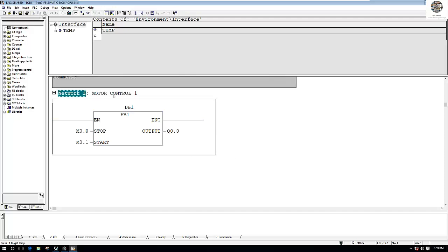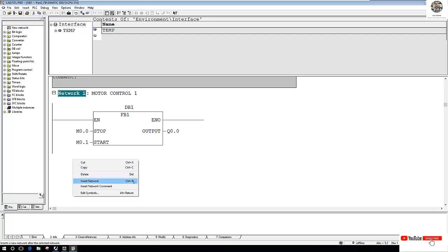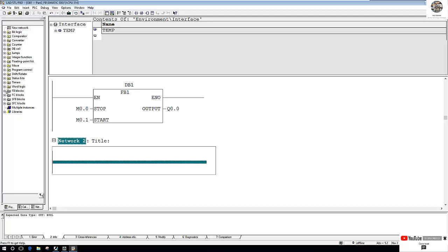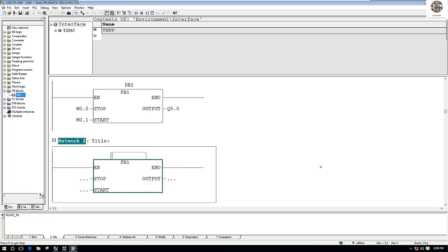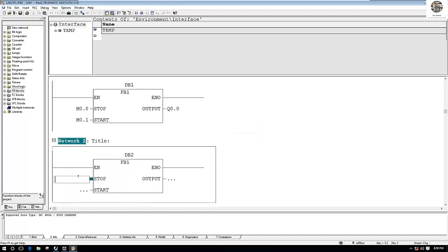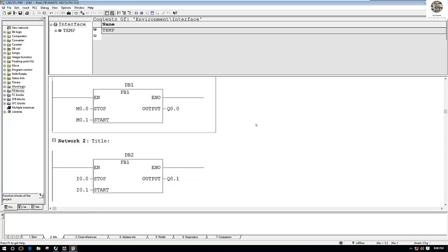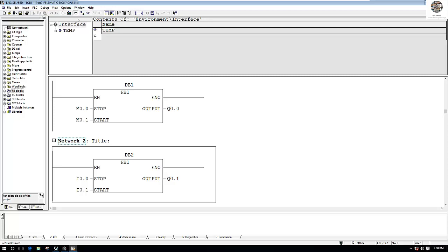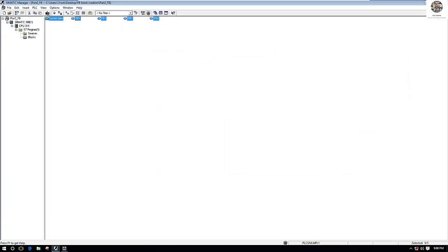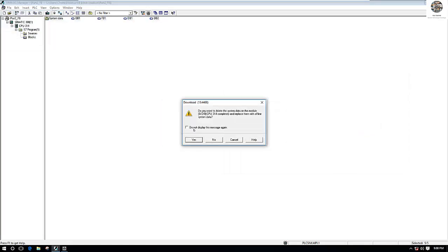So if we want to use this block to control motor number two, we just add network number two, then drag and drop this function block into it. For example, DB2 — and assign: I0.0 for stop input, I0.1 for start input, and Q0.1 for motor number two output. We must download again because we just added a new block.